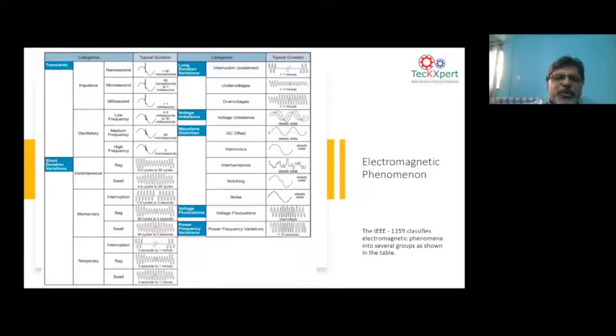Here again, if you look into the characterization, you have a low frequency, a medium frequency, a high frequency. That means you can characterize the oscillatory transient in terms of frequency, number two, in terms of magnitude, and number three, in terms of duration. So you can see all that mentioned in the definition. It is in milliseconds, less than 20 milliseconds, or maybe a little more than 20 milliseconds. That means these all remain non-steady state power quality disturbances on the waveform.